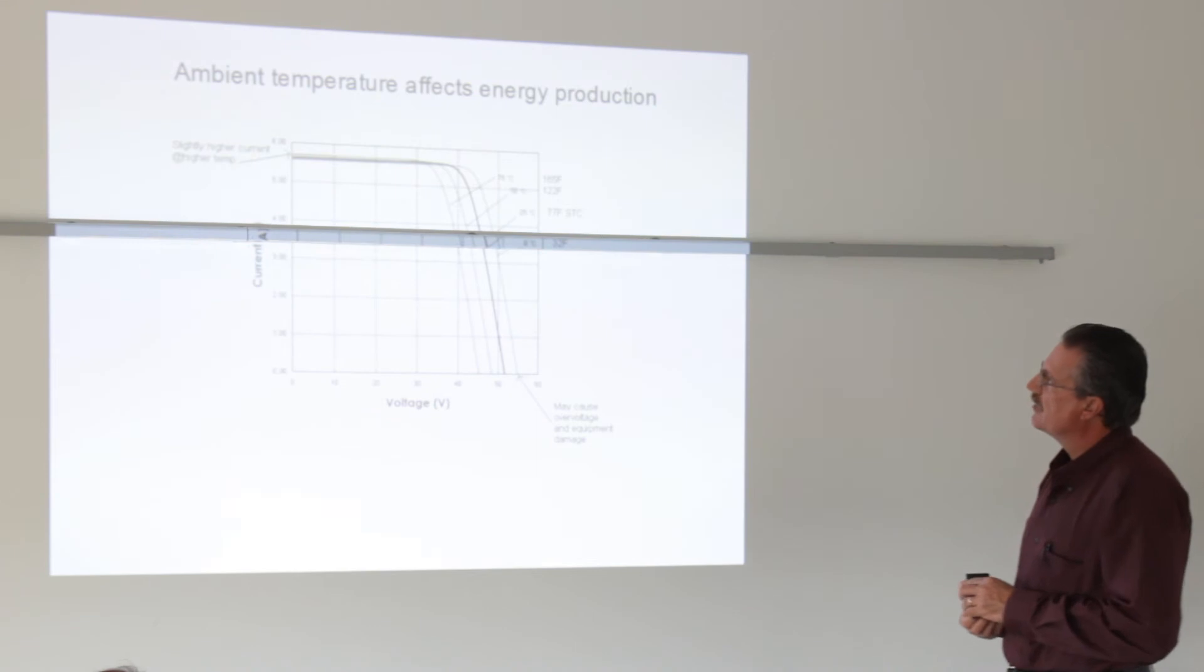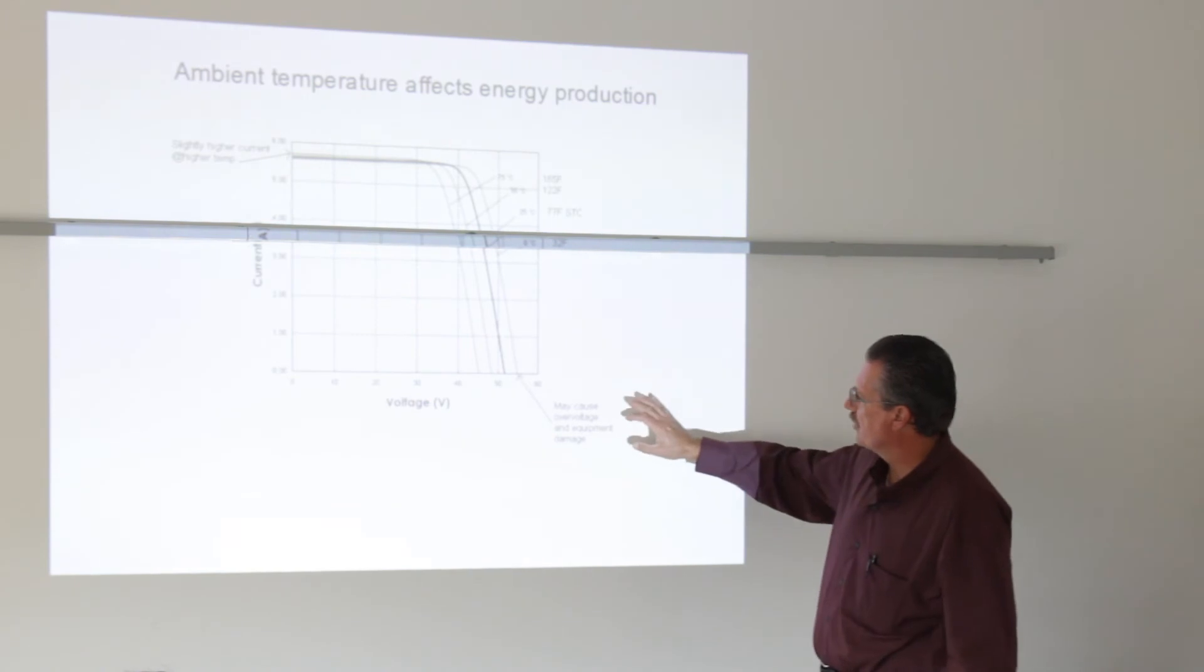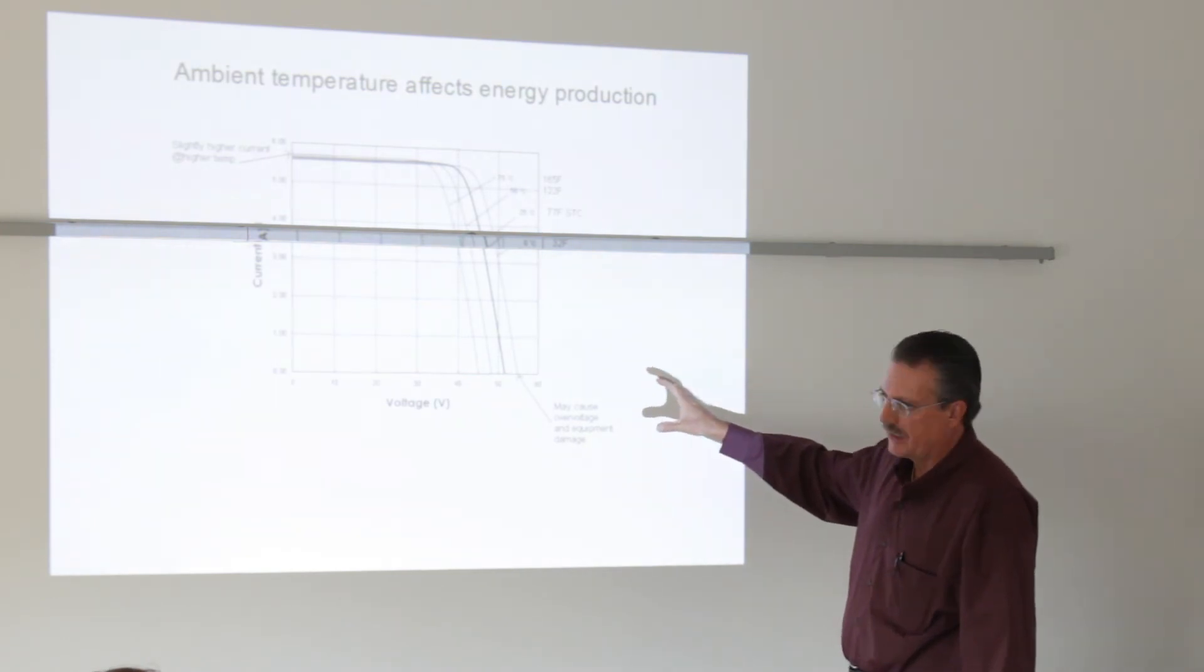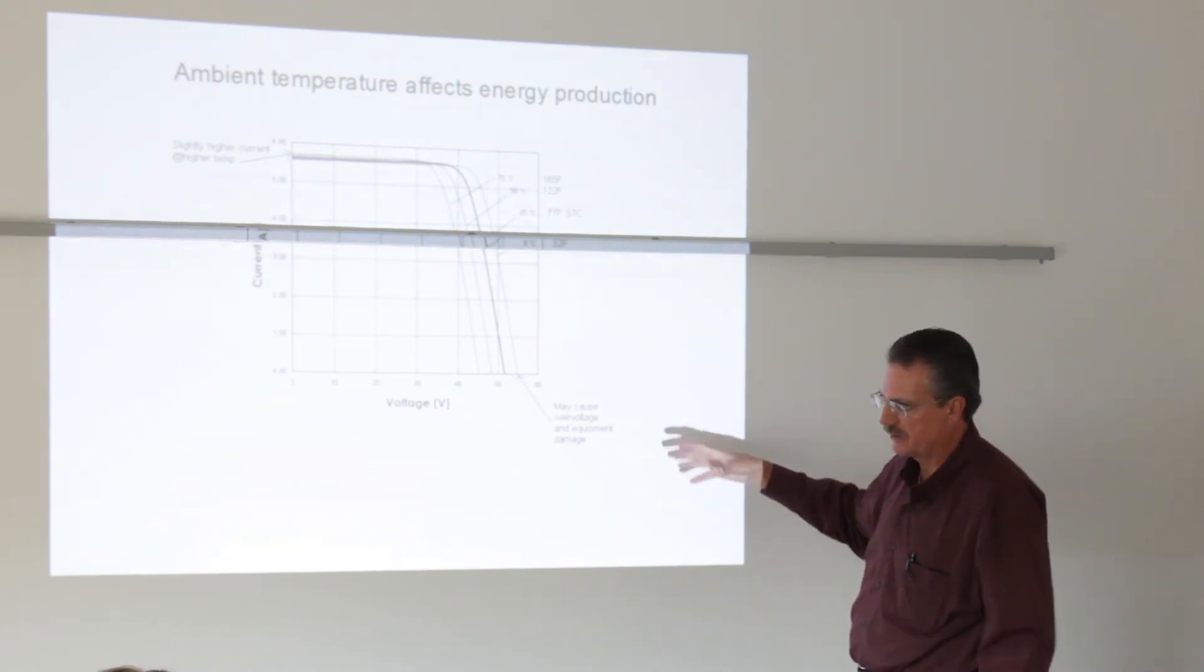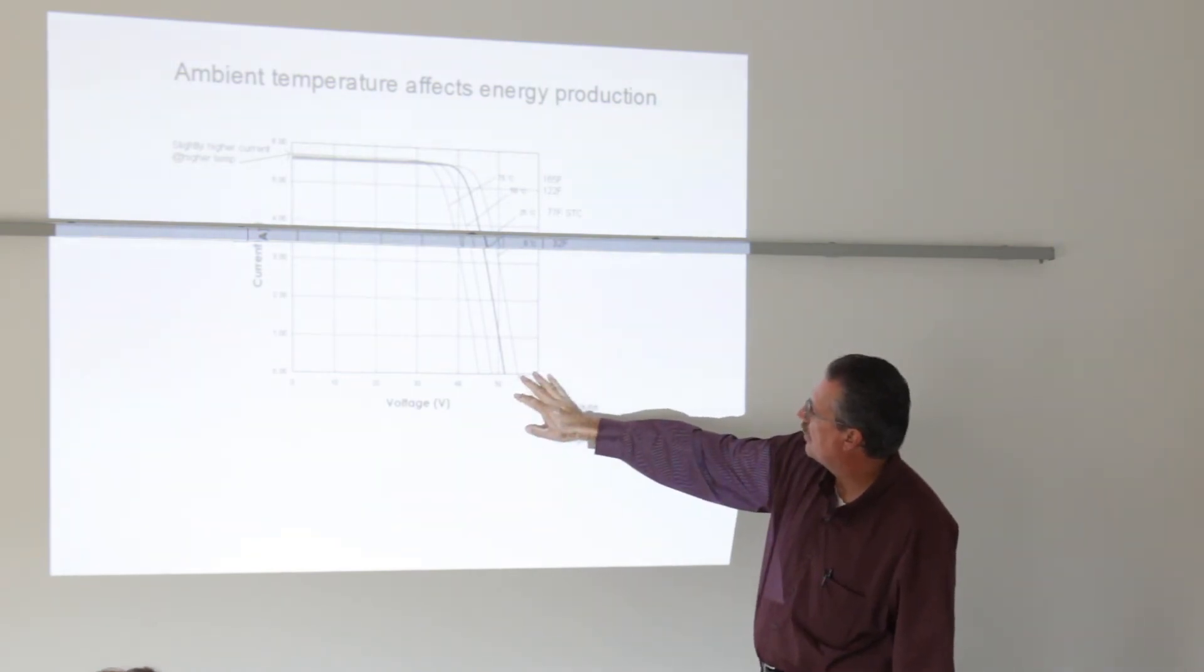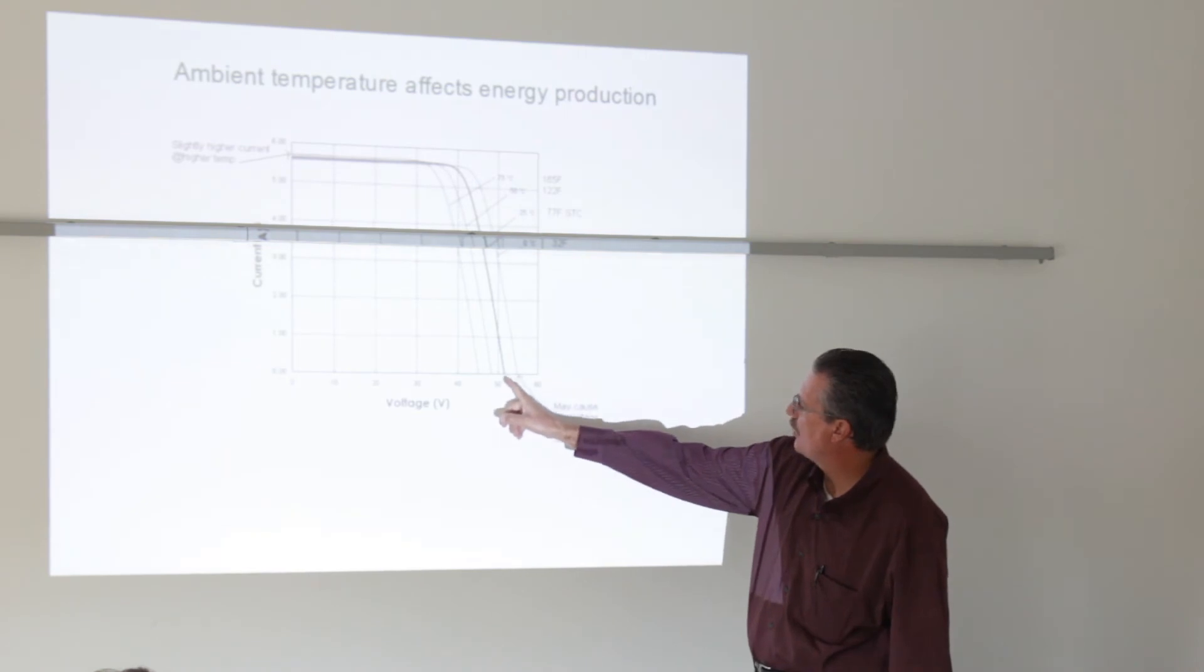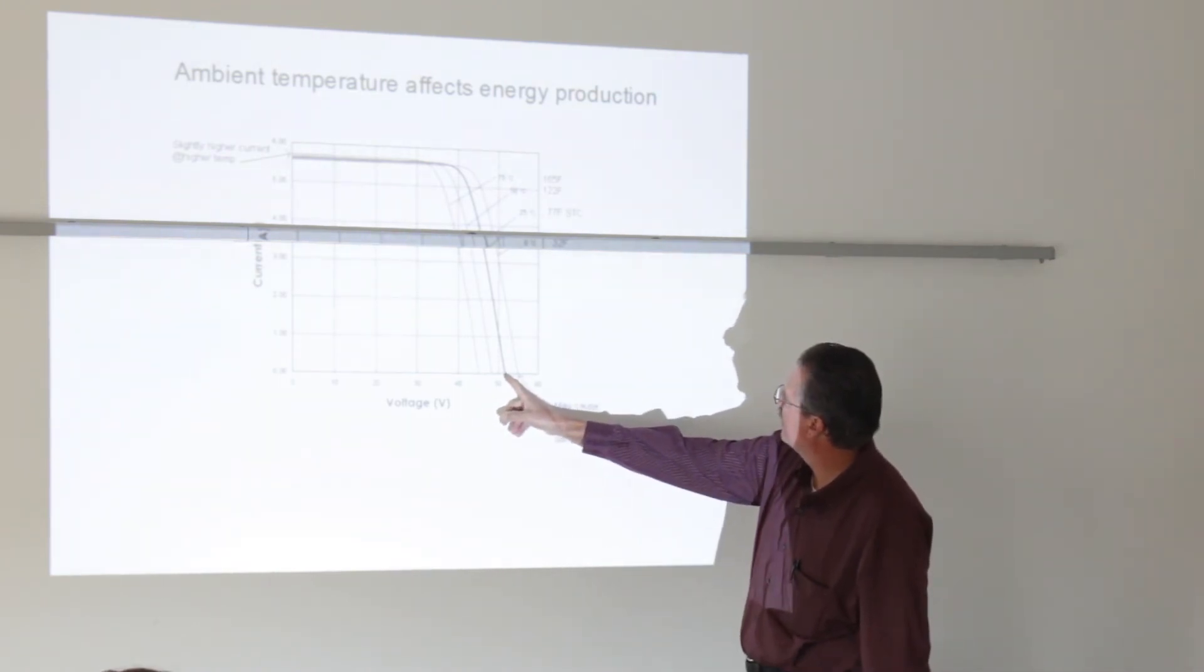I talked about how ambient temperature affects energy production. This is a Sanyo 210-watt module. I wanted just to highlight how important it is when you start factoring in various design criteria, why ambient temperature is very important. And especially with the way the National Electric Code's been rewritten for 2011, it's even more important now when it comes to the logistics of wiring and conduit and things like that. As the module gets warmer, you will have an energy decrease. As it gets colder, you will have an energy increase. Modules are tested at 25 degrees Celsius or 77 degrees Fahrenheit.